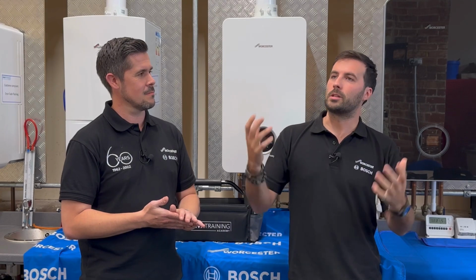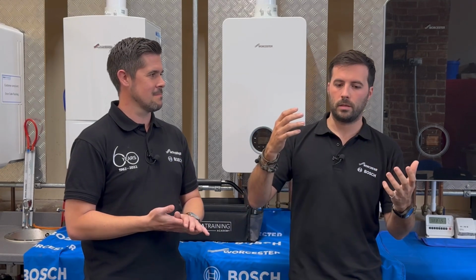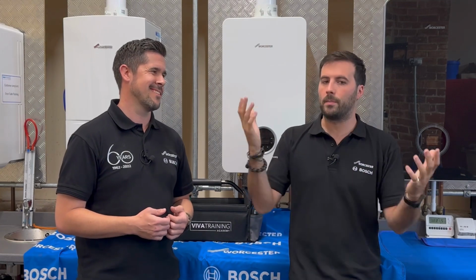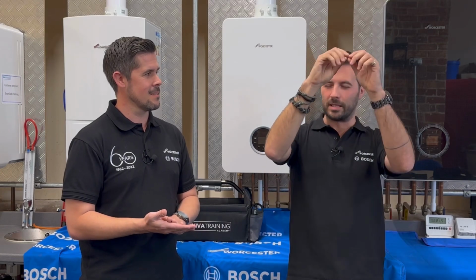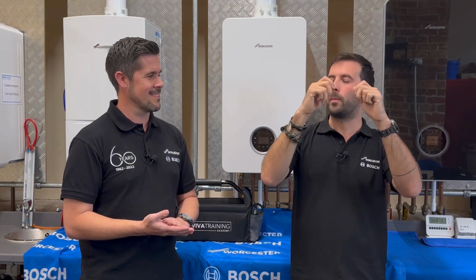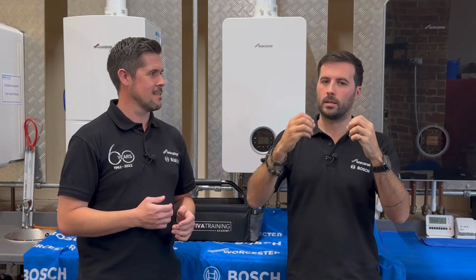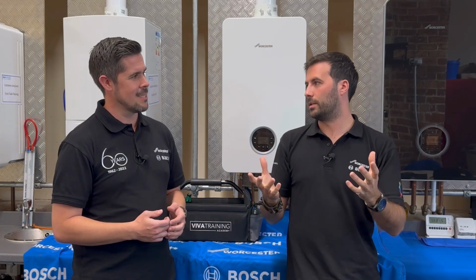If they had a fault and the system was running dry for a period of time, they might start to develop then, but then you top it up, you look after it, and it's absolutely fine. Yeah. So just because you see ripples doesn't mean there's an issue. But if you see ripples and then you've got all this staining down it, or you've got this tarry stuff coming out the top, that's where it's got so bad that water's starting to expand out of it. That is a failed heat exchanger.